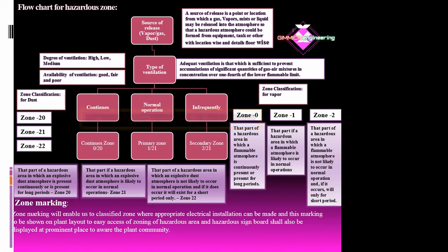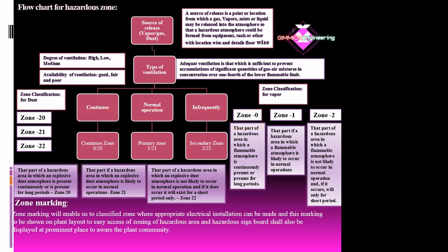So normally we refer to the service floor, electrical panels, offices, or what we normally use as a control room. Okay, and if the gas mixture in the air is less than 25% of LEL of continuous, then it is considered an adequate ventilation area. So the percentage of LEL we have to maintain should be less than 25%. Okay, so this is about the ventilation system and the source of release. Okay, Ajit, next slide.